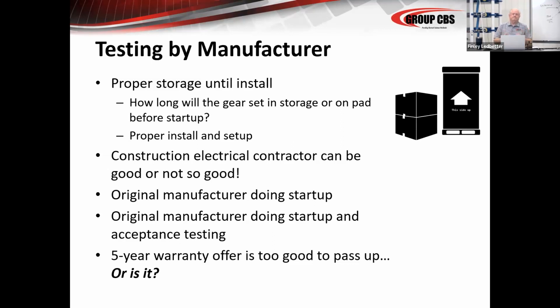Is that wise? Well, what they offer you normally is an extended warranty if you let them do the acceptance testing. So for that additional warranty, you get some, I would say, advantages, and you get some disadvantages. The advantages might be that you get the original manufacturer's support very quickly when they find a deficiency or a missing component. And the disadvantage might be that you may not hear about every problem. You may not see every problem because they may handle it internally and not disclose it to you. So there are some advantages and disadvantages with having the original manufacturer involved in the startup and acceptance testing.